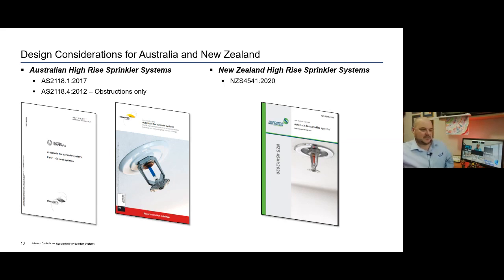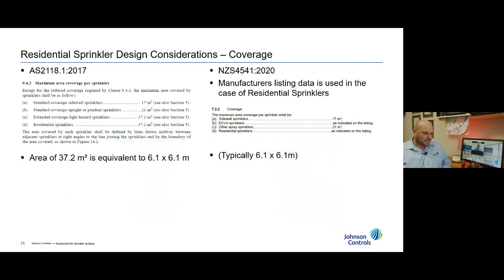The other standard that we use in this area is the New Zealand standard 4541. If New Zealand people are still listening in, I know it's been very Australian today, so my apologies to our Kiwi cousins, but certainly 4541 allows the use of residential sprinklers as well in these light hazard areas. So I've got up there on the screen the AS2118.1:2017 and New Zealand 4541. In terms of the coverage areas that we're talking about, you can see that they're very similar.